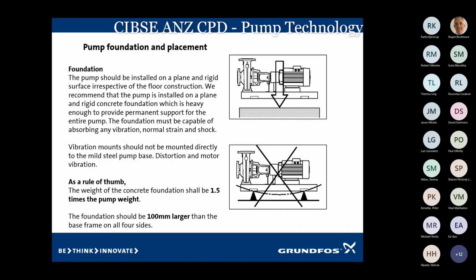stabilizing it. When the system's filling and moving, you've got air moving around in the system, and the pump is running up and down the curve. It's bouncing backwards and forwards, and that's just putting a lot of stress back onto the pump and the mechanical seals. So when you start up a new system or a new pump, any pump, get the discharge valve, close it off, and just crack it open slightly, run the pump, let it settle, and then open up the valve and let it go from there.